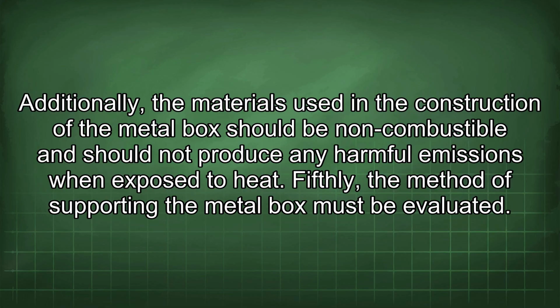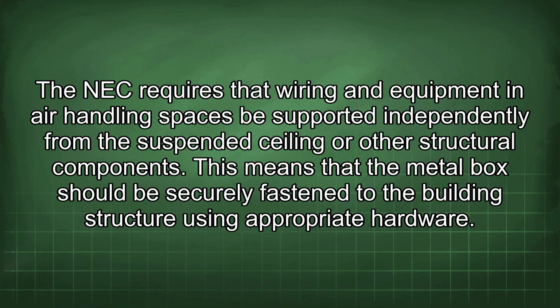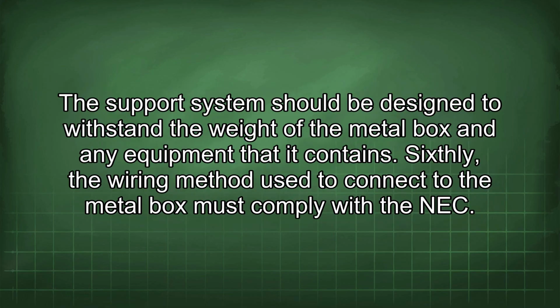Fifthly, the method of supporting the metal box must be evaluated. The NEC requires that wiring and equipment in air handling spaces be supported independently from the suspended ceiling or other structural components. This means that the metal box should be securely fastened to the building structure using appropriate hardware. The support system should be designed to withstand the weight of the metal box and any equipment that it contains.